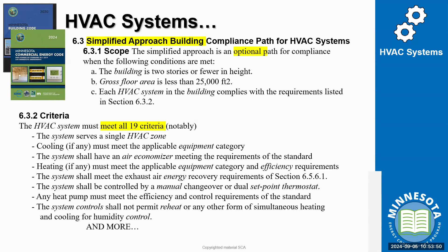So simplified buildings have the flexibility to follow this compliance path and those identified criteria. As mandatory expectations within the code, we're looking at three basic things: equipment efficiency, calculation, and location. Efficiency of the equipment is where we comply with tables 6.8.1 through 20. If it's a non-standard piece of equipment, it has its own expectations for efficiencies, and then there are calculations associated with those layouts, plus distribution and location. So those are your main three concepts—whenever you think about mechanical systems, think about efficiency, equipment itself, its calculation, its controls, and location.